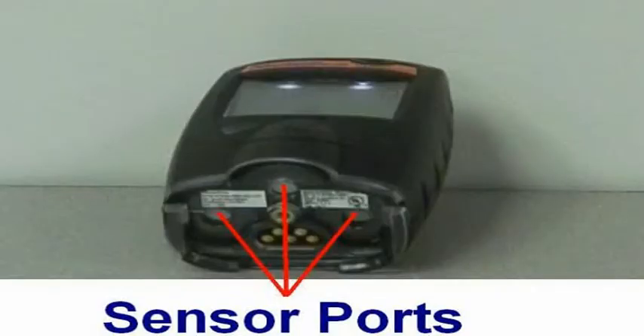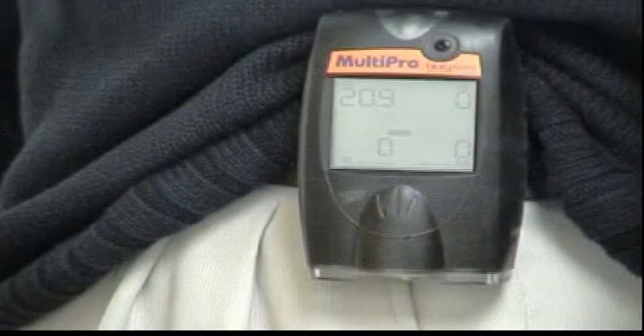The MultiPro can be used in either diffusion or sample draw mode. In either mode, the gas sample must reach the sensors for the instrument to register a gas reading. The sensors are located at the bottom of the instrument. Each sensor has its own sensor port. In diffusion mode, the atmosphere being measured reaches the sensors by diffusing through the sensor ports. Normal air movements are enough to carry the sample to the sensors.